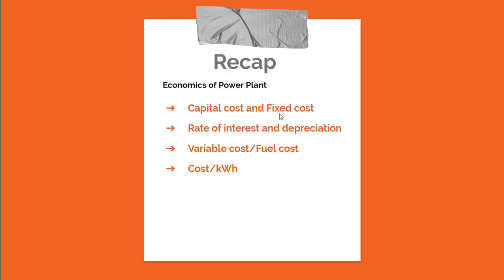And we said that the fixed cost is independent of the hours of usage, because even if you have a power plant and if you don't generate electricity out of it, you would anyway be paying the bank the rate of interest and the plant would be anyway depreciating. It means the judicious way of operating the power plant is to see that the operating hours are increased so that the component of fixed cost gets reduced.